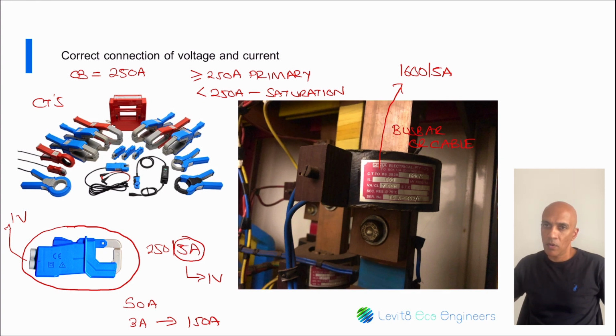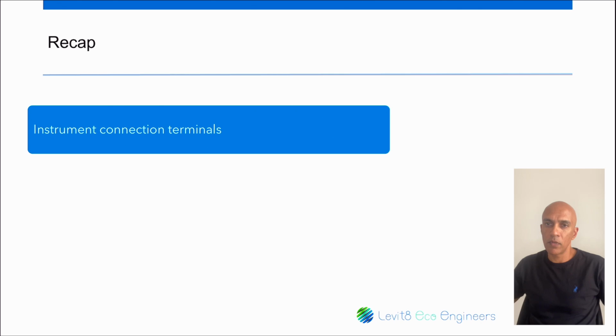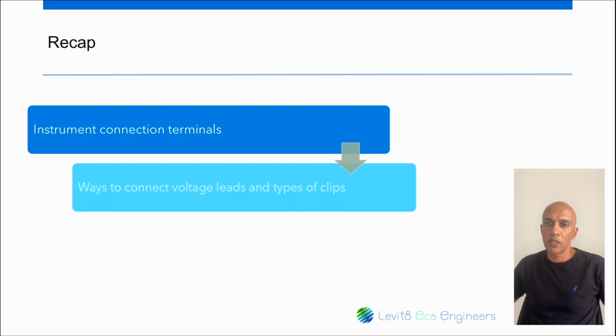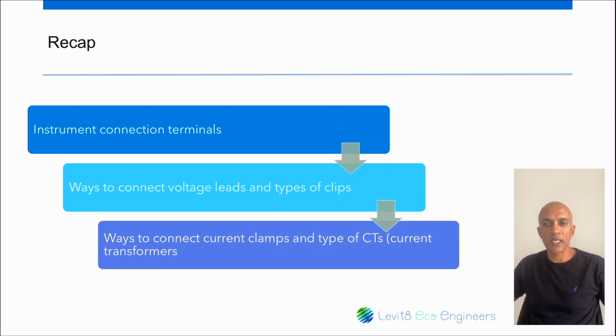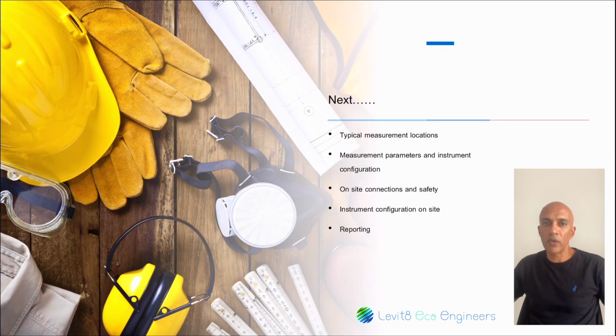So, what have we covered here now? We have covered instrument connection terminals, the ways to connect voltage leads and the type of clips that you can use, and the ways to connect current clamps and the type of CTs or current transformers that you will use. Now, in the next video, we'll look at the typical measurement locations, the measurement parameters and instrument configurations, the on-site connections and safety, the instrument configuration on-site, and the reporting. Thank you, and I'll see you in the next video.